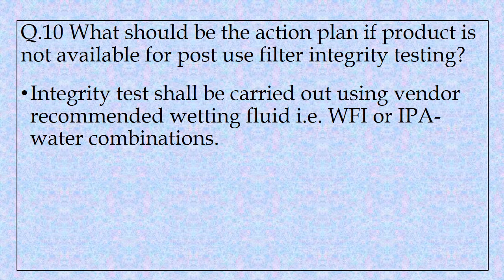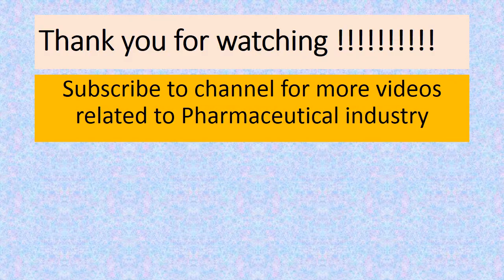Question 10: What should be the action plan if the product is not available for post-use filter integrity testing? In this case, filter integrity testing shall be carried out using the vendor-recommended wetting fluid, that is WFI or IPA-water combinations. Please comment with your questions, and thank you for watching. Subscribe to the channel for more videos related to the pharmaceutical industry.